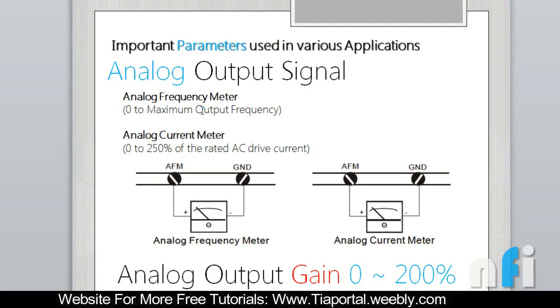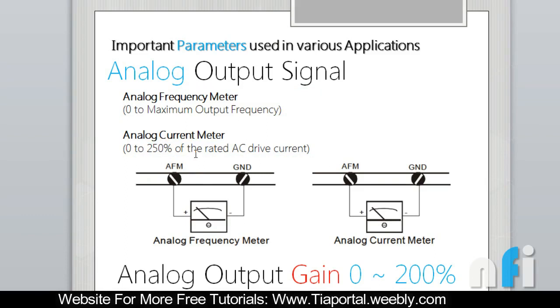You also have feedback based on current. In this mode you have 0 to 250 percent of the rated current of the drive. Based on the current you can read that feedback in your PLC, your HMI, or you can use a voltage display meter. Now in this video we are going to synchronize one drive based on the feedback from another drive.